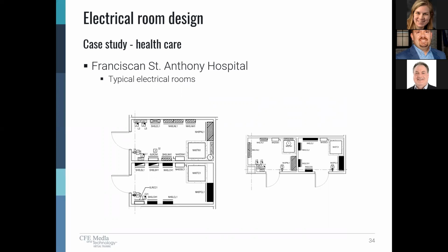We also considered the rating of the room in the instances where we had transformers over 112.5 kVA. In this particular example, we utilized transformers that included the 155 degrees C insulation, which didn't require any of these rooms to be rated.